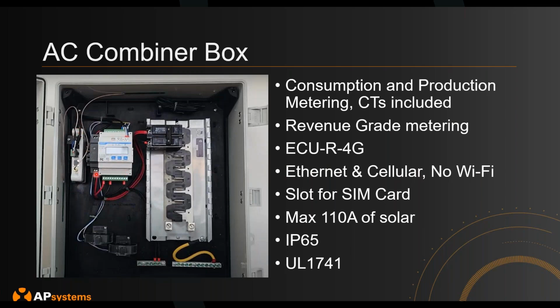This unit is a meter that allows you to do CT measurements. The PV CTs are over here, so you'd run the solar in through the breakers onto this box, which will actually replace the load center as well. You would also have CTs going externally to the main service panel to measure the consumption of the site.